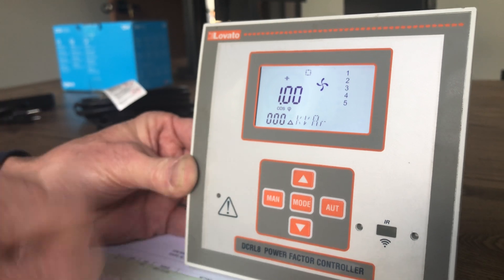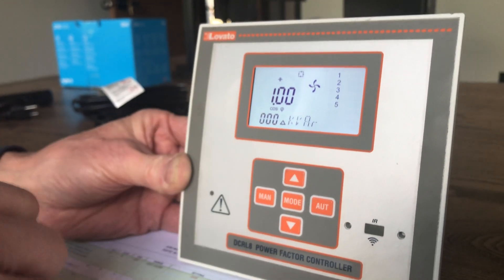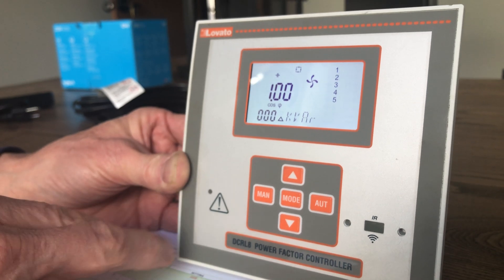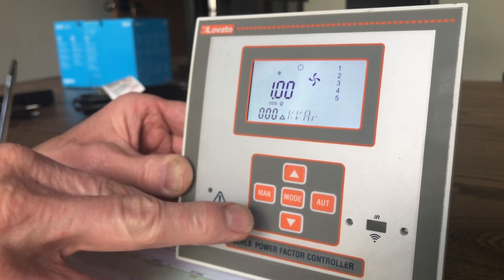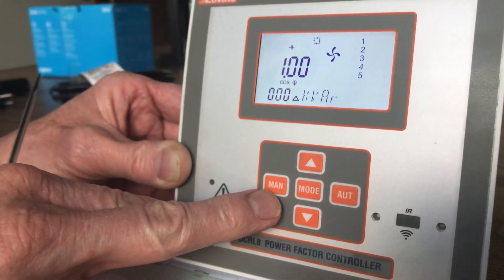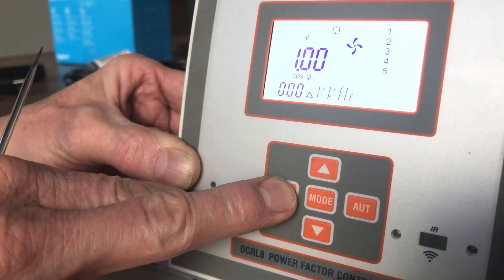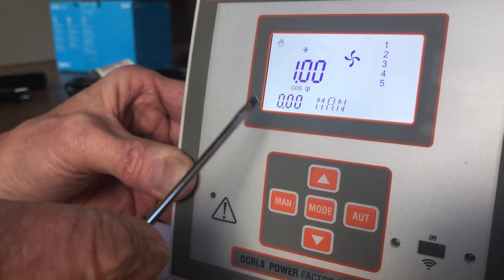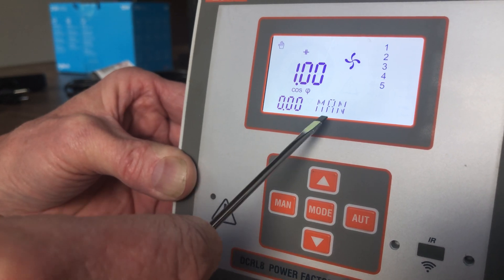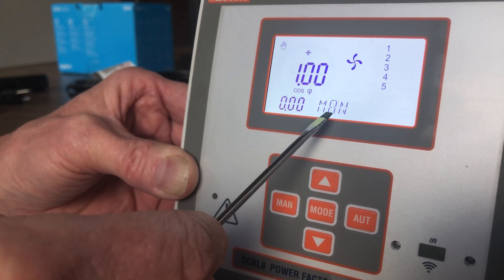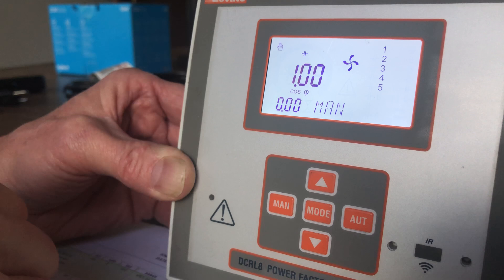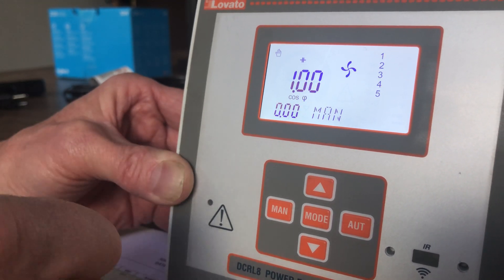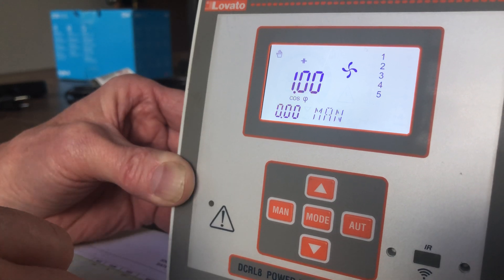If you need to make any changes or edit any of the parameters, the first thing we need to do is put it in manual mode. To do that, you'll see there's a manual button. You press and hold it, and now you see the delta kVAR has changed to MAN, indicating you're in manual mode. Now you're in a state where you can get in and edit some of these parameters.